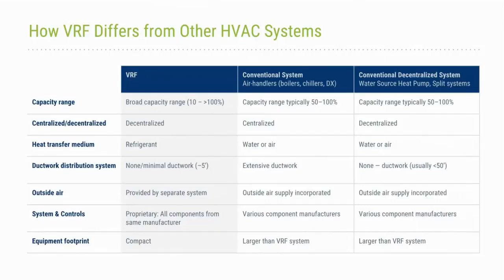Another significant difference is that conventional systems move heat through a building using water or air. VRF systems use refrigerant. Consequently, VRF systems use little to no ductwork. However, VRF systems do not include outside air. So either a completely separate outside air system is needed, or an outside air system needs to be integrated with the VRF system. Now, some renovations have taken advantage of existing ductwork and used it to provide outside air to spaces or to the indoor units.